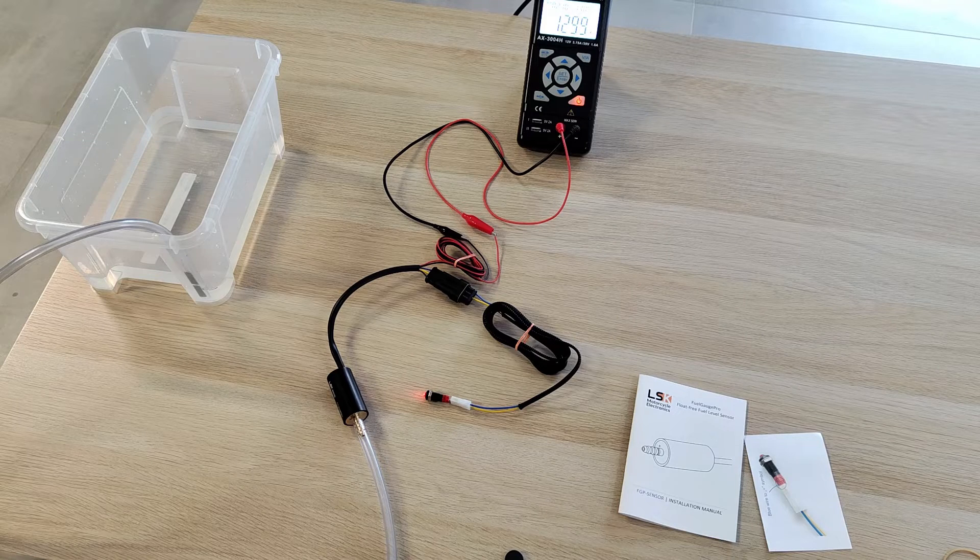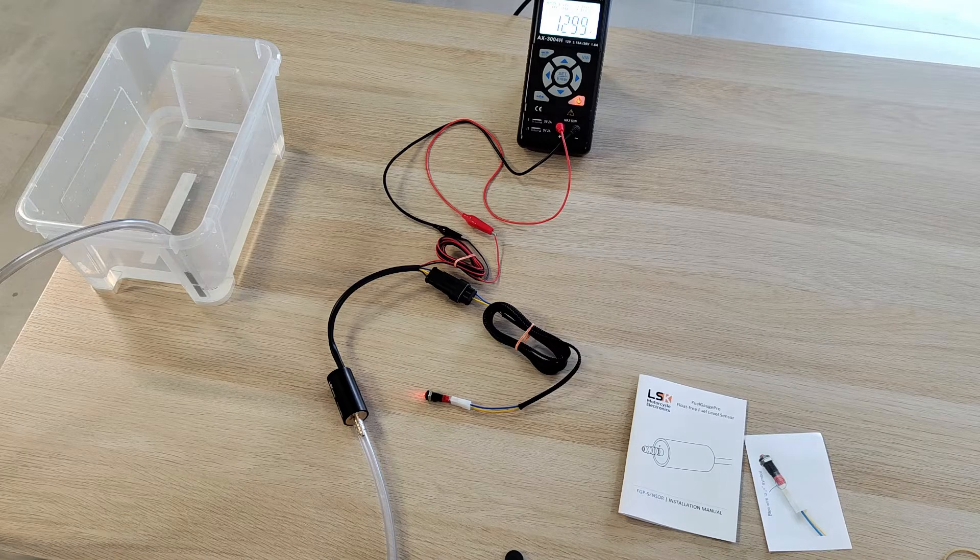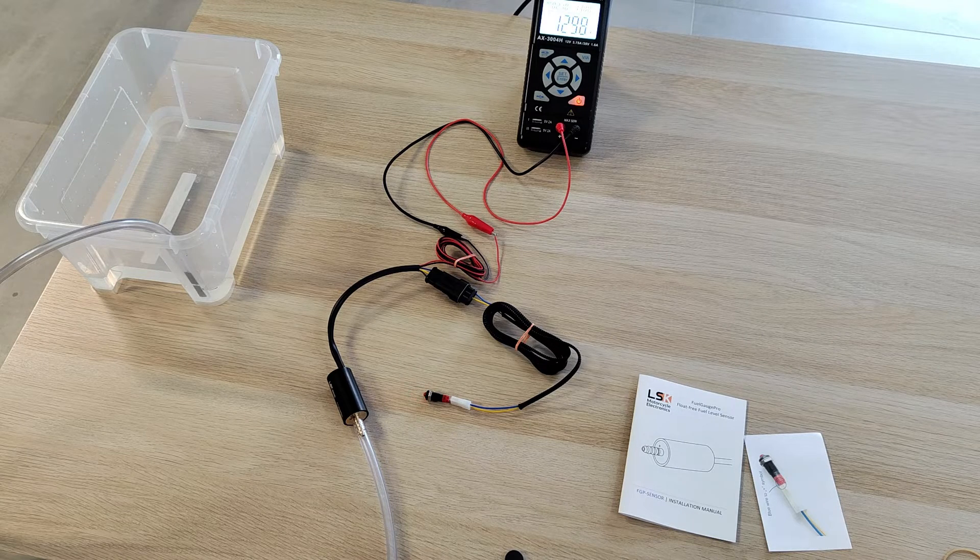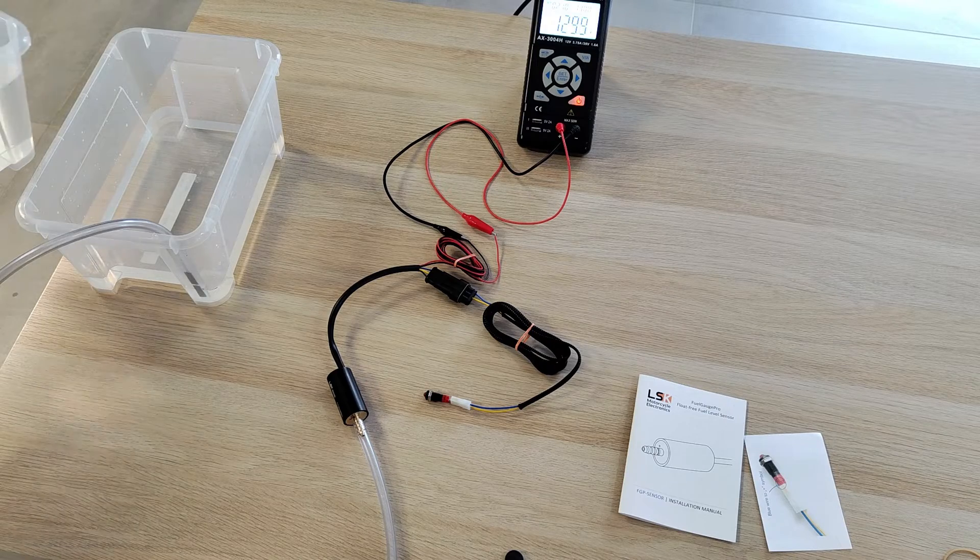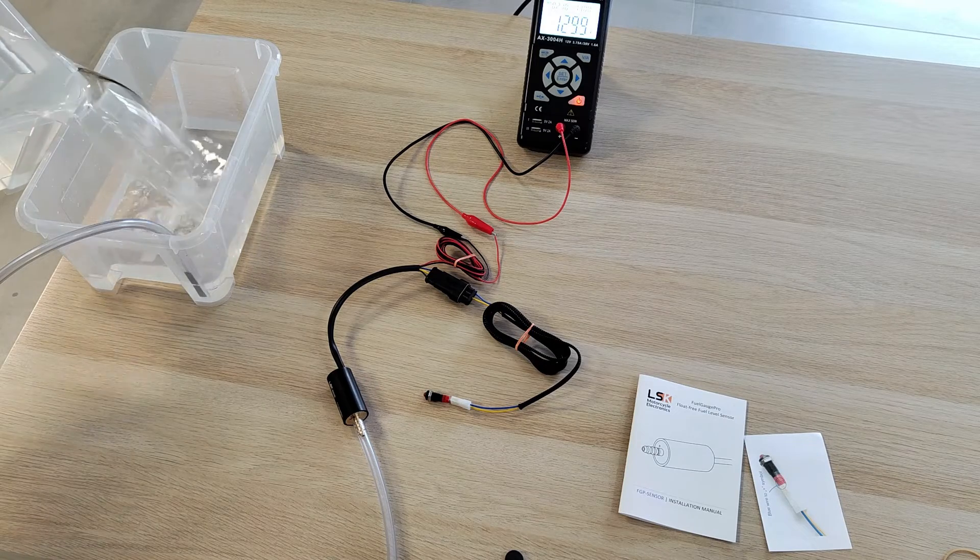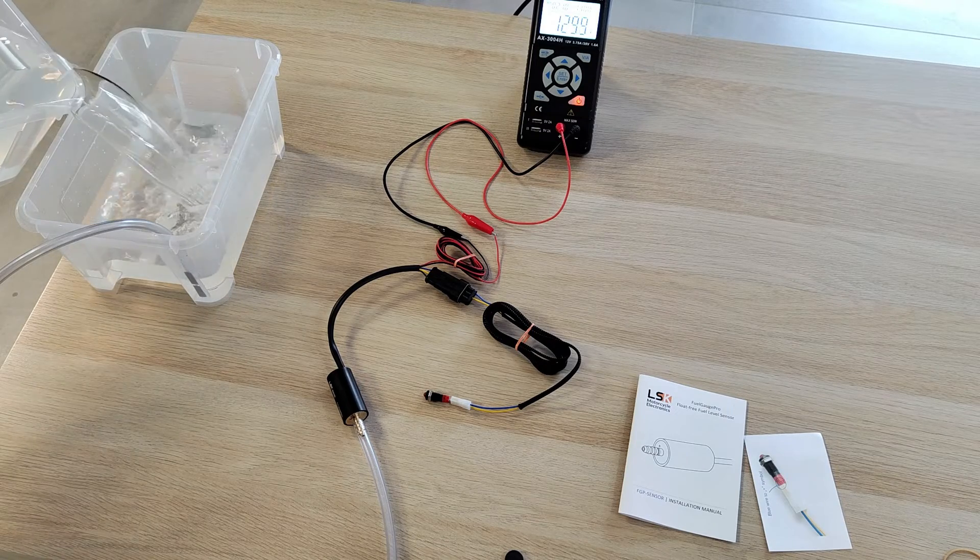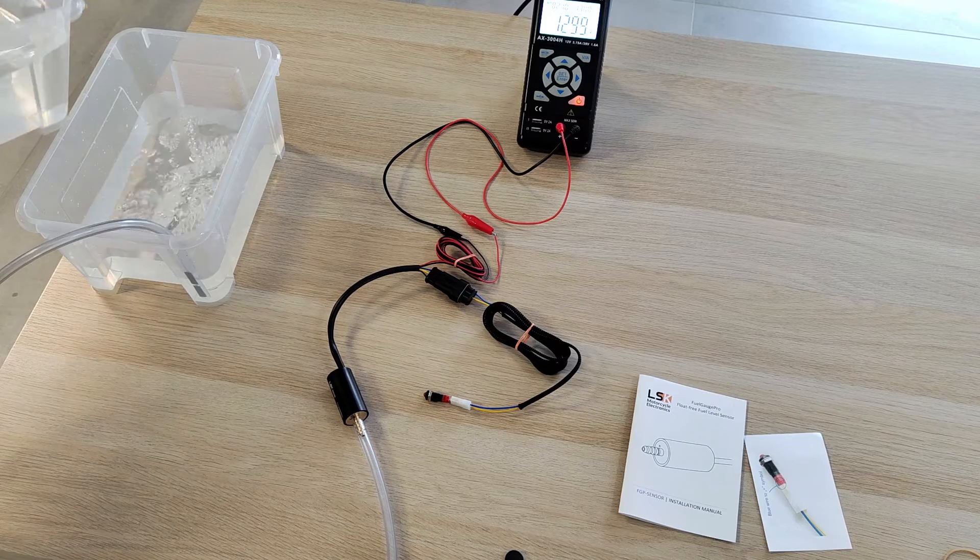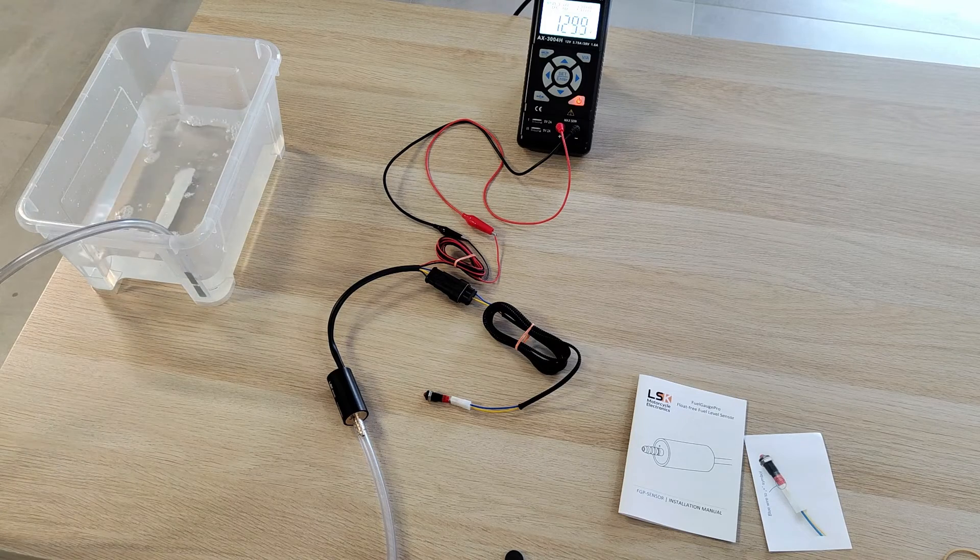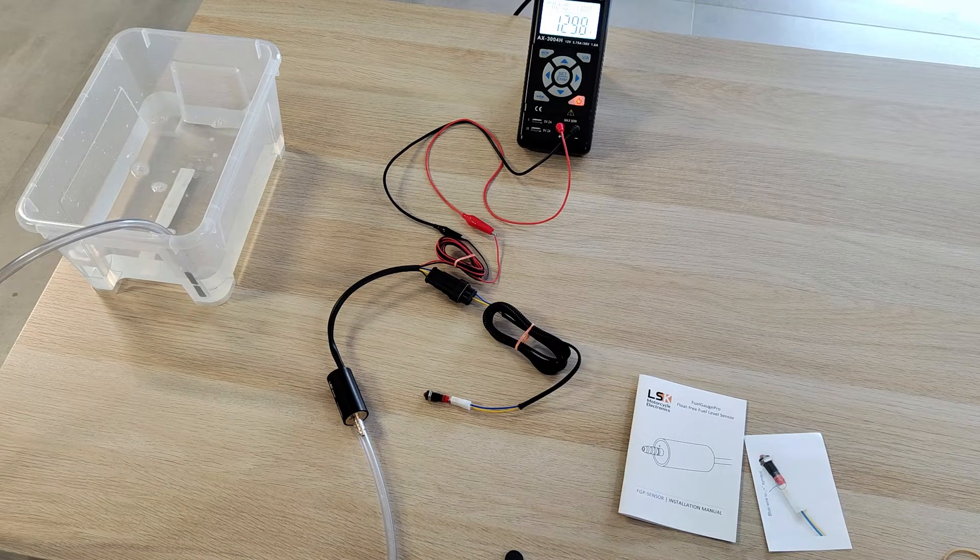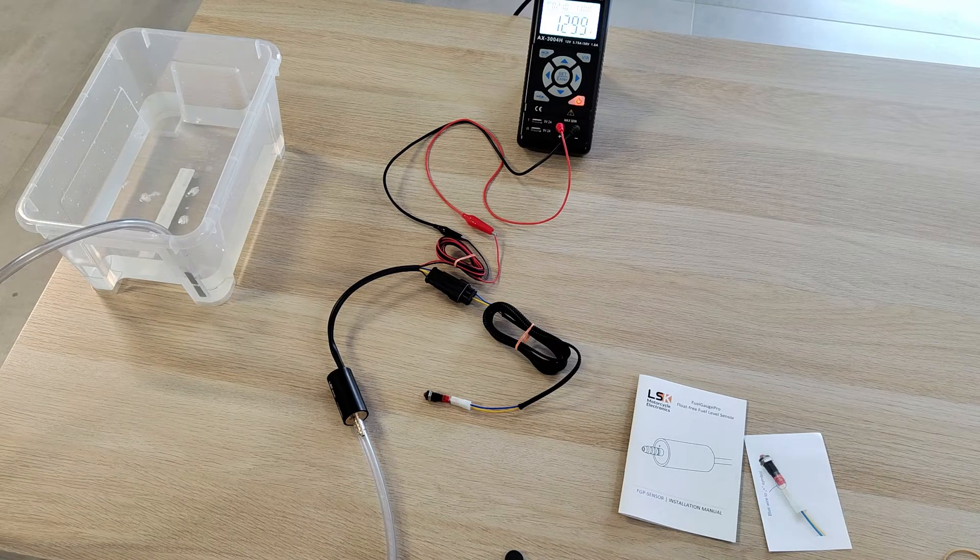Now the threshold is set and we can check its function. I'll add some more fuel and as you can see, the LED is off.